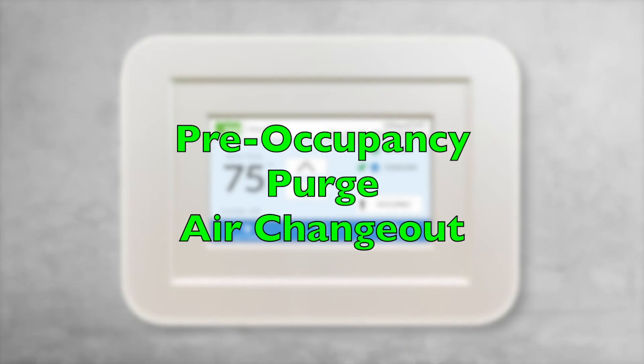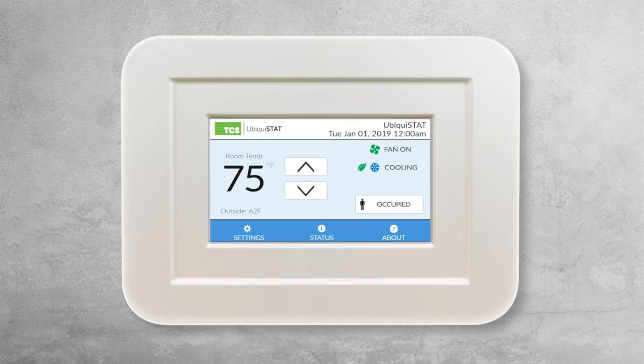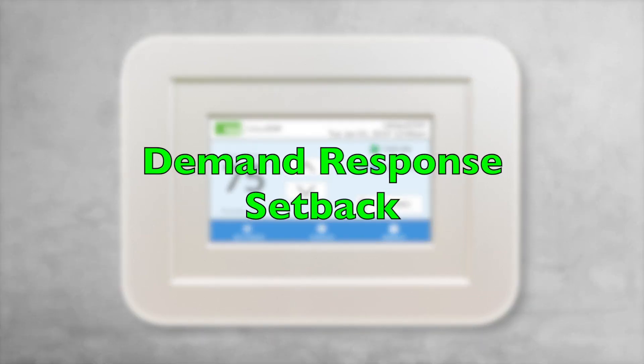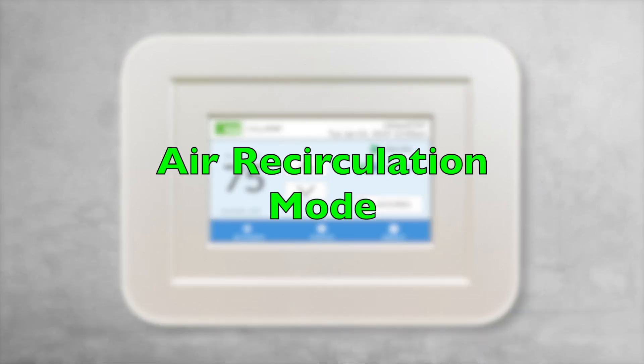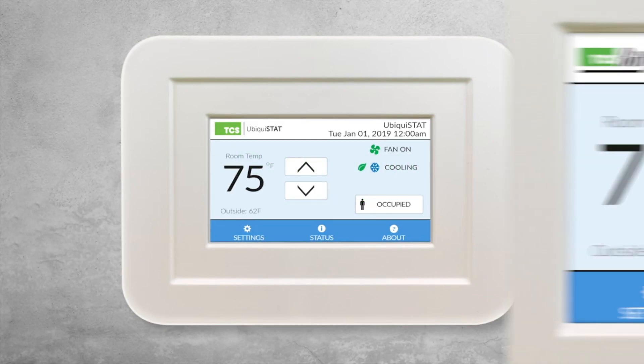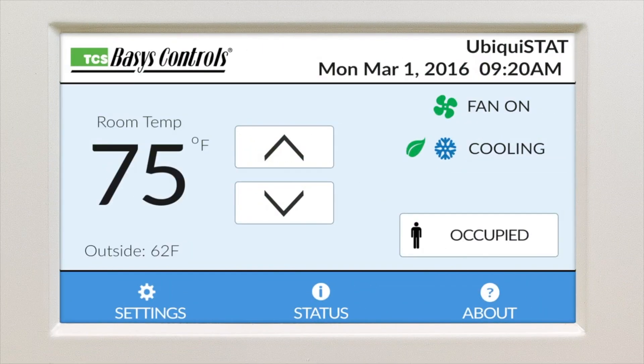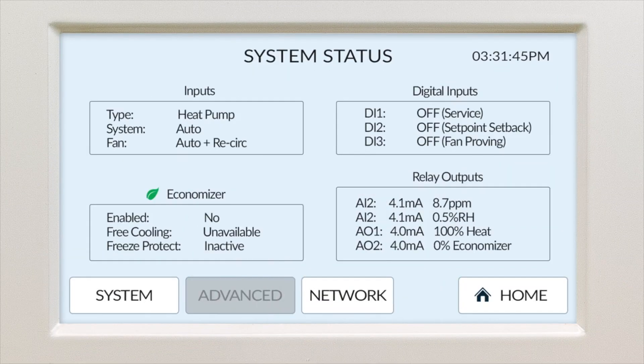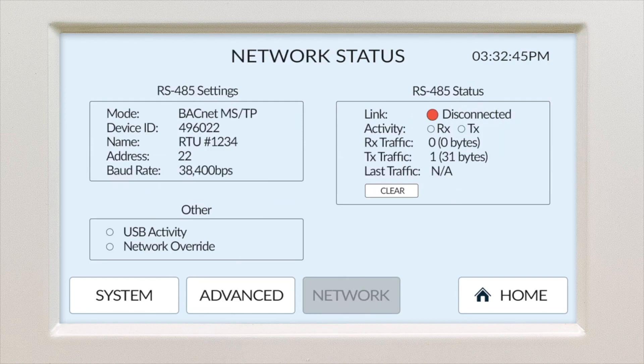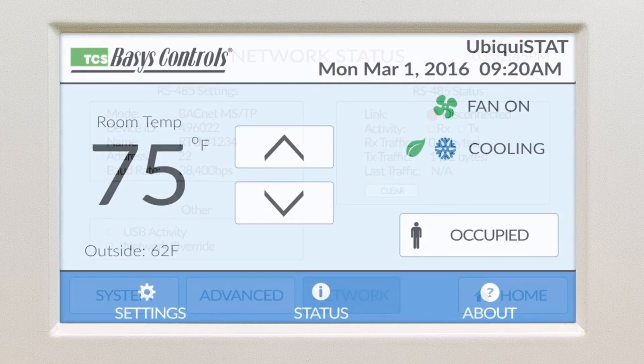Modulating zone damper with modulating reheat valve control. Pre-occupancy purge. Demand response setback. Air recirculation mode to meet minimum fresh air requirements. We also developed other great features, such as advanced status screens, which show every point, including network activity, which can help diagnose BACnet MSTP, TCS bus, and BACnet Wi-Fi communications.